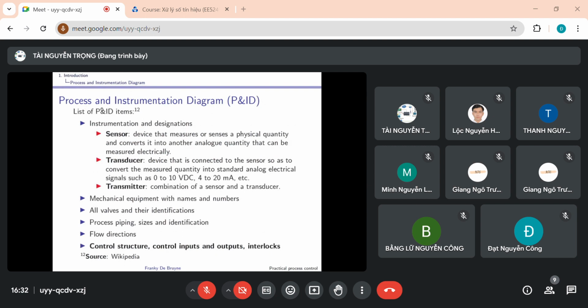Here is a list of items that you can find in a P&ID. You'll have information about the instrumentation, so the sensor, the type of transducer, the type of analog electrical signal, mechanical equipment with names and numbers, all valves with their identifications, process piping, sizes and identification, flow directions of material, and of course, very important for us control engineers, the control structure. So the control inputs, outputs, interlocks, feed forward, cascades, and things like that.